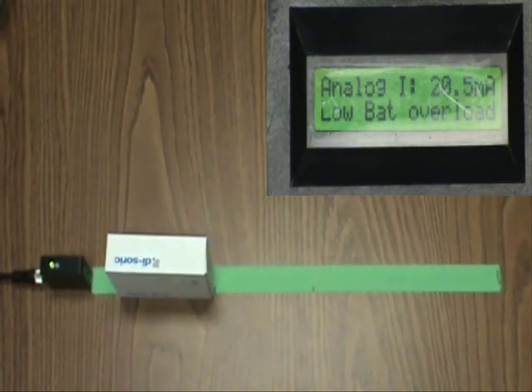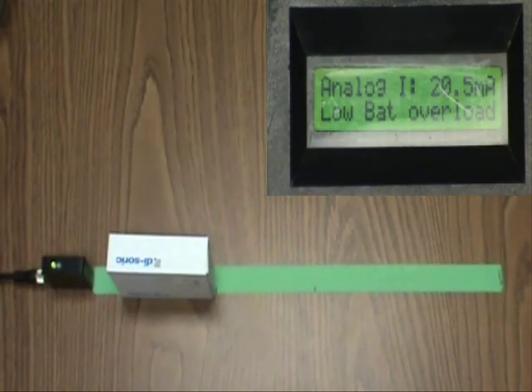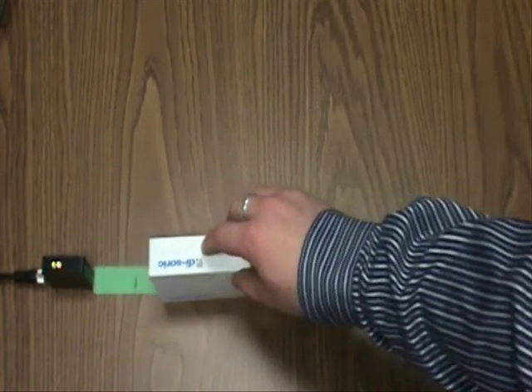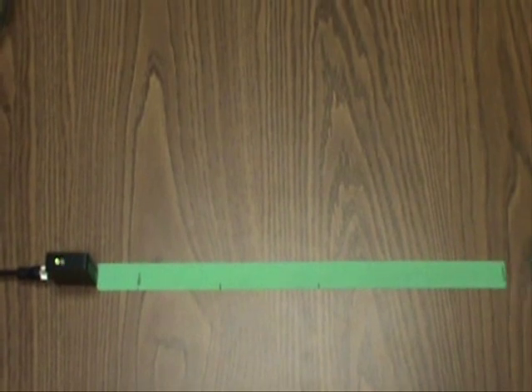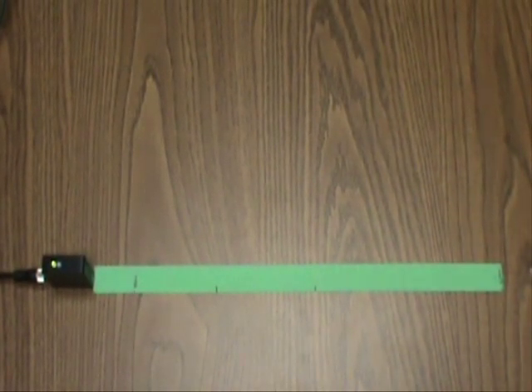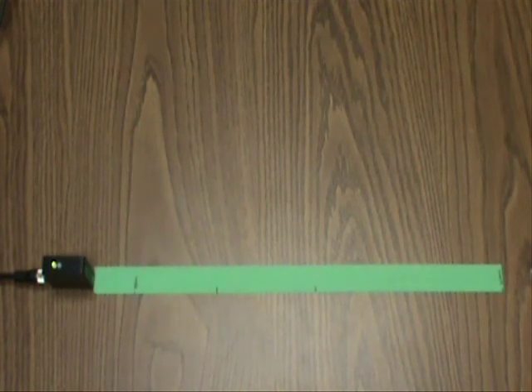That is, it now triggers a 20.5mA output. Similarly, to the other side of the sensor, it also triggers a 20.5mA output, indicating that the object that we are trying to sense is outside of the sensing range of 50mm to 500mm.